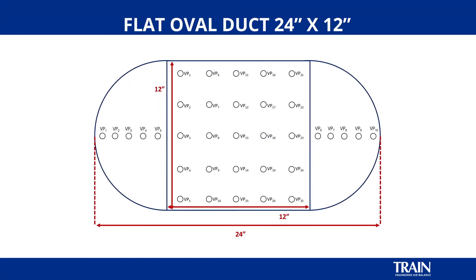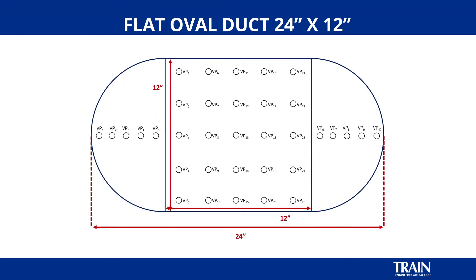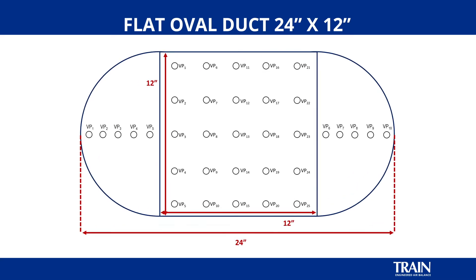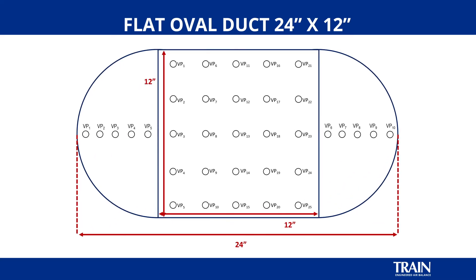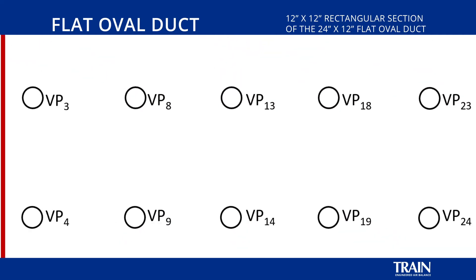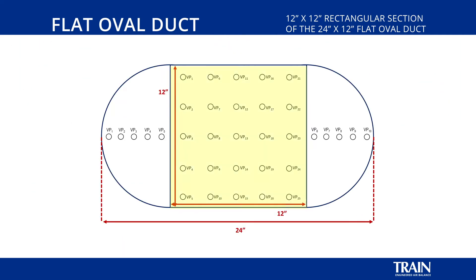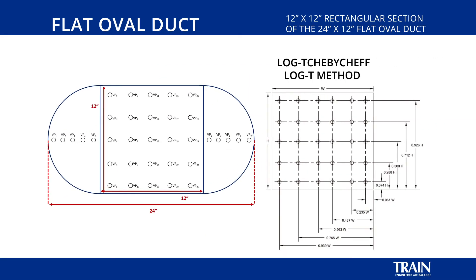For our next real world example, we will be demonstrating how to mark the pitot tube for a 24 inch wide by 12 inch tall flat oval duct. To do this, we're going to be first marking our pitot tube for the rectangular section of the flat oval duct. We will be referencing the log Chebyshev method.